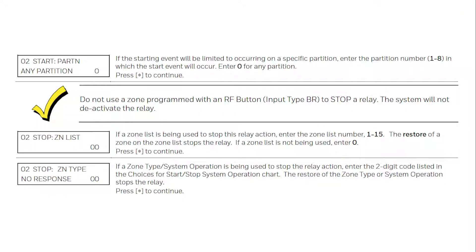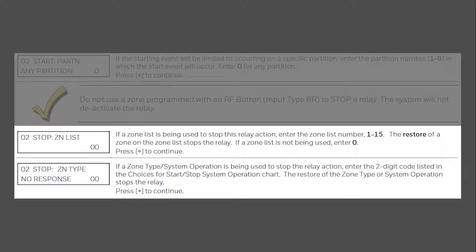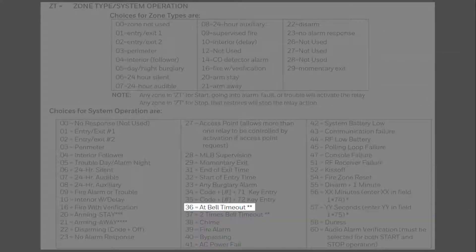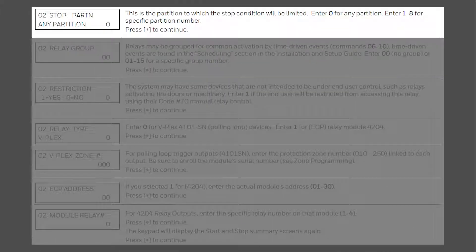If the relay was programmed to start on a zone number and the condition is met while the panel is disarmed, the relay will restore when the zone is restored. If the panel is armed when the condition is met, then the relay will not change state until a code and off is entered. If you activated the relay with a zone list or zone type, choose the corresponding action to change the relay back to its original state. It can be on the restore of a zone within a specific zone list, or a zone type such as zone type 36, which is bell timeout or code and off, whichever happens first. Press star. Enter the partition that this stop action needs to originate from, then press star.